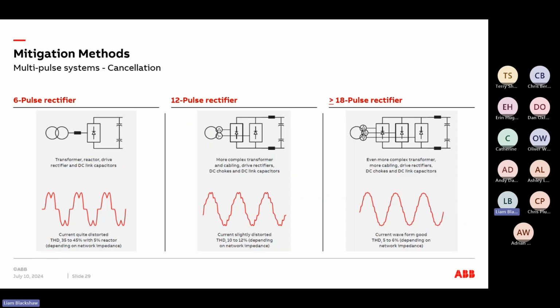A couple of things as well, again related to drives, just to be aware of. This one is what we call multi-pulse systems, which was a means to cancel out harmonics on a system. It was an old traditional way of eliminating harmonics when you had a large power drive on a system, where you would have either a 12 pulse or greater than 18 pulses, with a complex transformer system with multiple secondary windings, sets of drive rectifiers, the DC link and capacitors. And you can see at the bottom that the more levels of rectification there were, the more the current distortion became less, at least anyway.